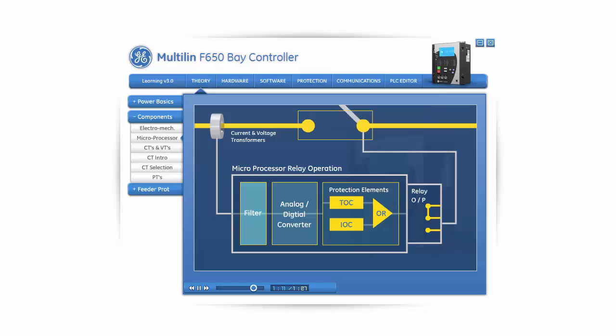The type and number of protective elements within a particular relay will depend upon the type of protective application the relay has been designed for. For example, a relay designed to protect a transformer will have some protective elements not found in a relay designed to protect a feeder, and vice versa.